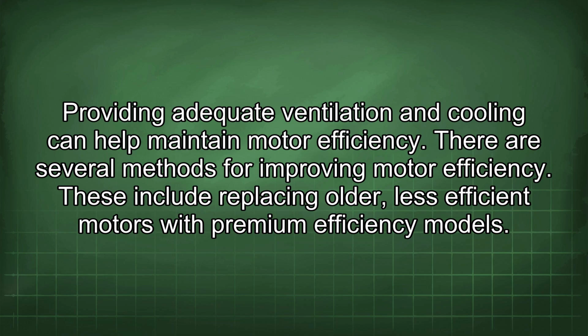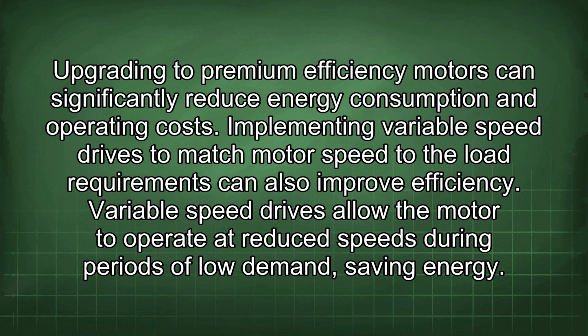There are several methods for improving motor efficiency. These include replacing older, less efficient motors with premium efficiency models. Upgrading to premium efficiency motors can significantly reduce energy consumption and operating costs. Implementing variable speed drives to match motor speed to the load requirements can also improve efficiency. Variable speed drives allow the motor to operate at reduced speeds during periods of low demand, saving energy.